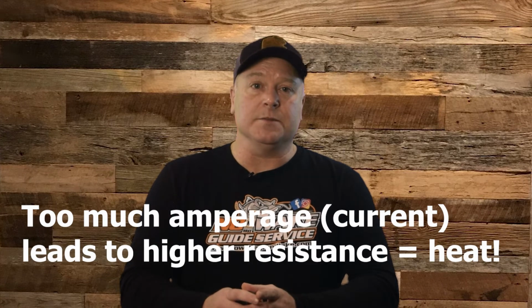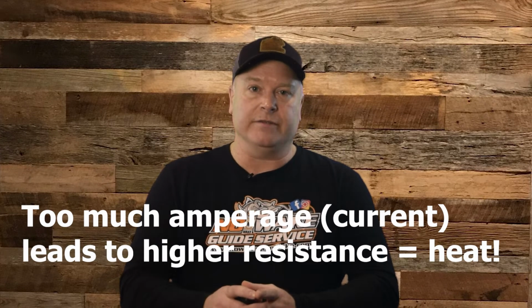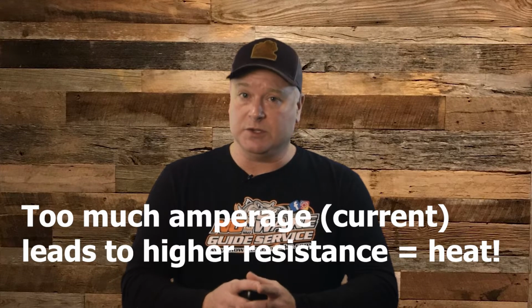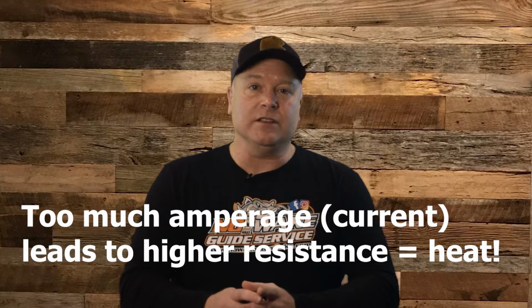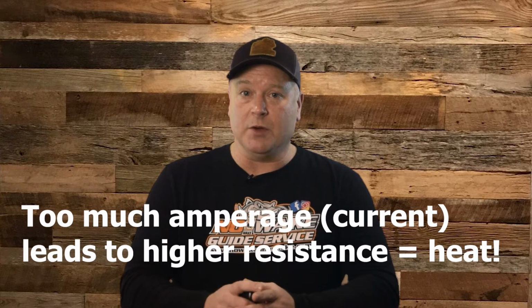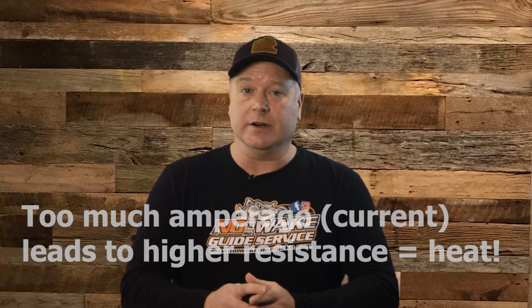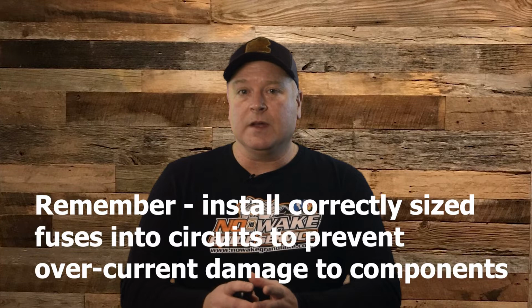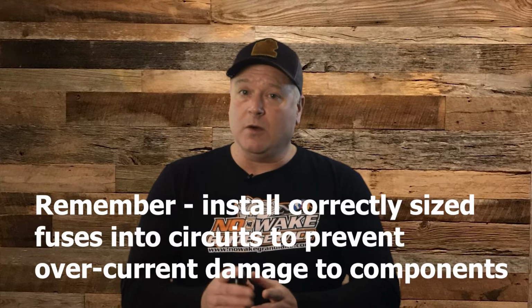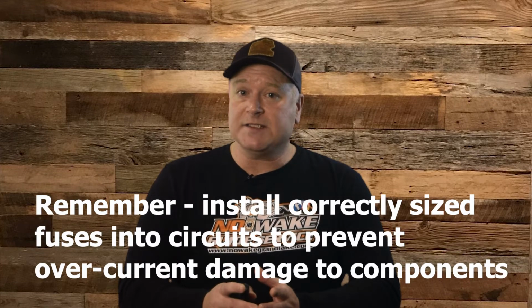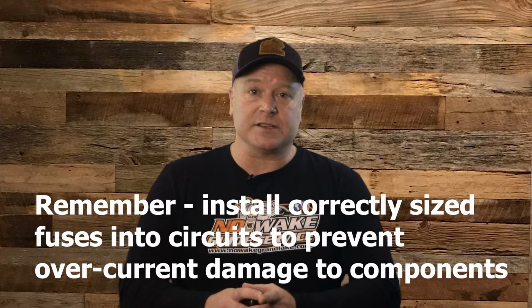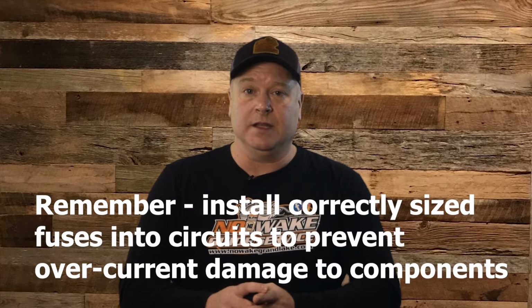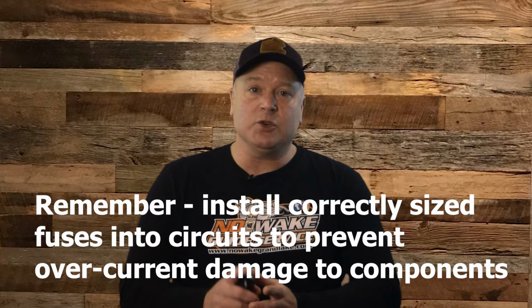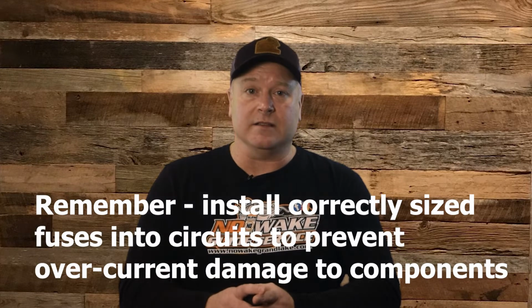Well, your wiring may start to become hot, especially if it's not large enough, and it can even start to melt. Also, switches that are close to their rated capacity could start to melt as well. I've even seen the fuses in a converter melt because the amp load exceeded the rated capacity of the converter. This type of problem doesn't always happen right away. It can happen over time, especially if you run your battery voltages low on a regular basis. And when it does happen, it usually is not an easy fix, and it can ruin components in your system. So to avoid this condition, make sure you have your circuit sized to avoid excessive amperage loads.